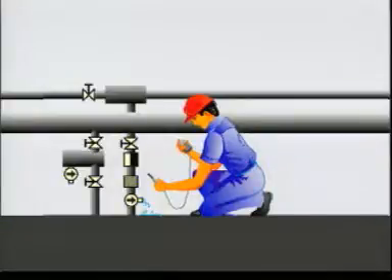To observe the system's response to your different actions, measure the temperature of the return water. You should always try to keep the intended temperature using as few coils as possible and with lowest possible steam pressure.